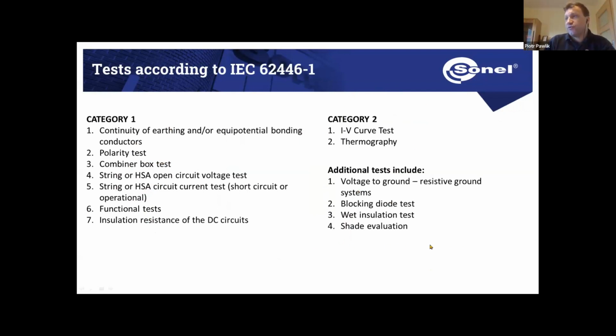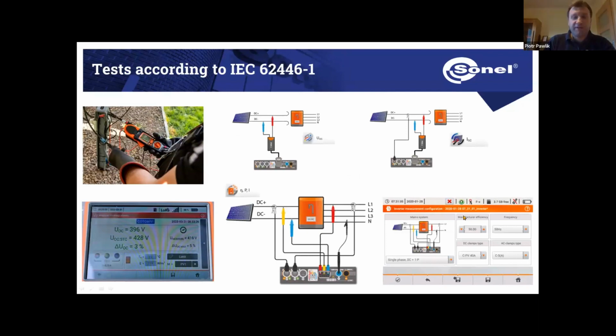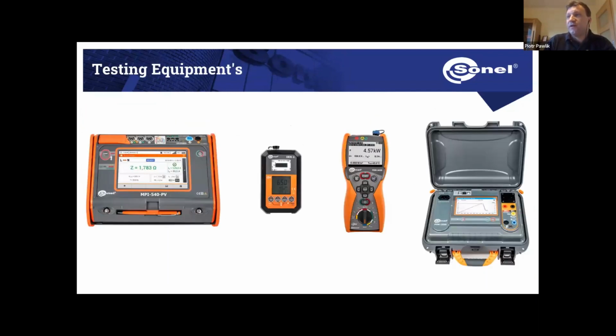Optional tests are category 2 and additional ones, and they include current voltage curve, thermographical tests, and additional tests, voltage to ground, blocking diode, insulation in wet conditions, and shade evaluation. So we can do all of that with our multifunction meters MPI 540 PV. However, if you are making tests only on photovoltaic installations and you are not interested in all the AC part, you can look at our PVM meters.